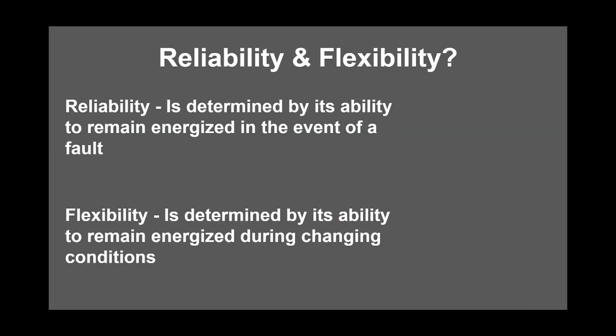Reliability and flexibility. A substation's reliability is determined by its ability to remain energized in the event of a fault. For example, if there is a fault on the bus and the whole substation goes down, then reliability is low. A substation's flexibility is determined by its ability to remain energized during changing conditions. For example, if a single breaker in the substation needs to be serviced, will the whole substation need to be de-energized? Or can you do a partial outage where customers downstream are not affected by this?